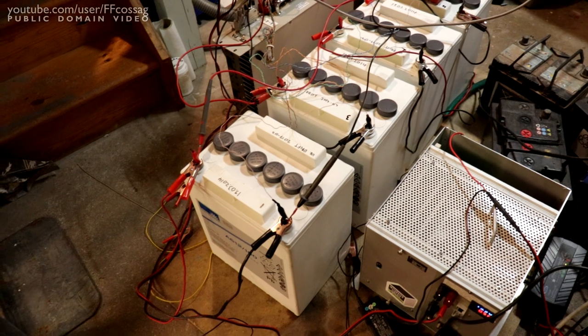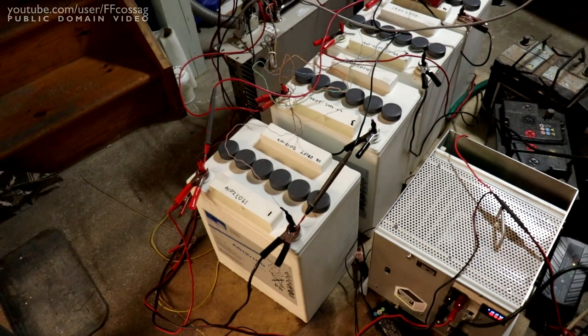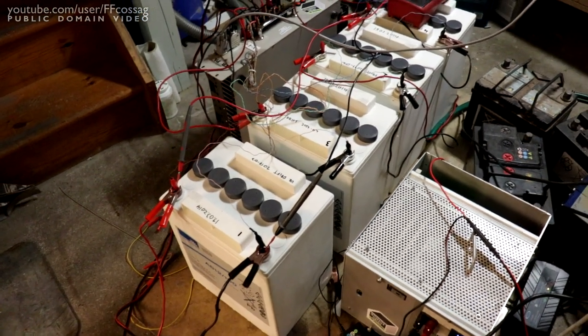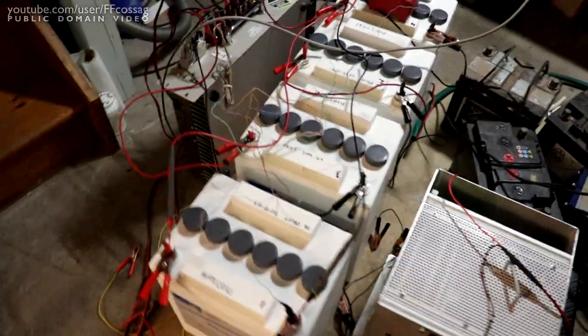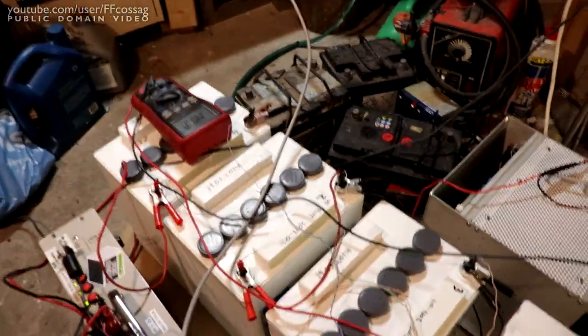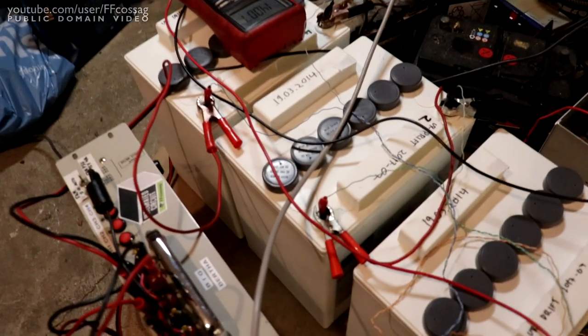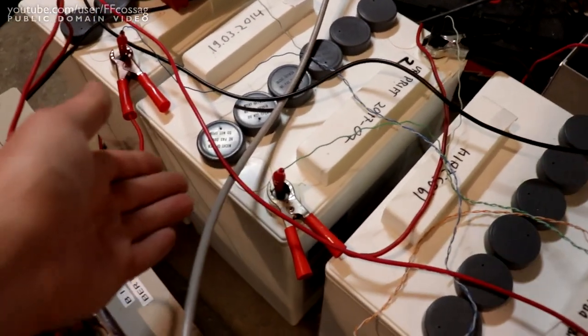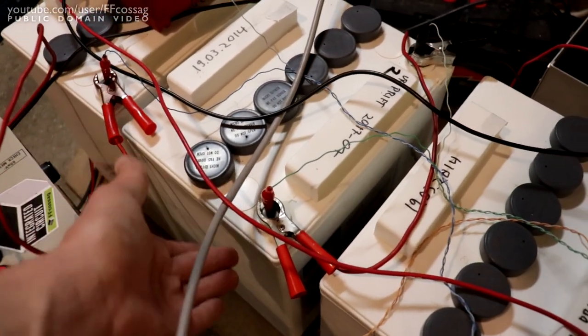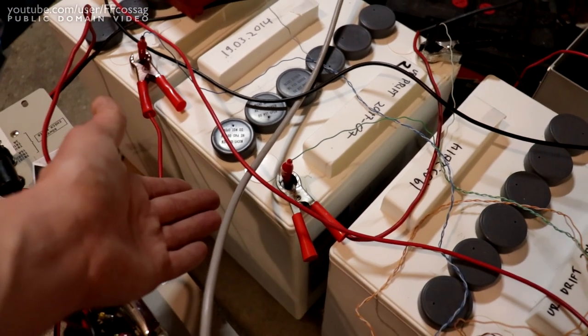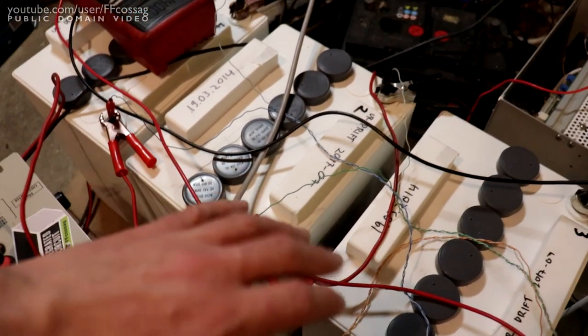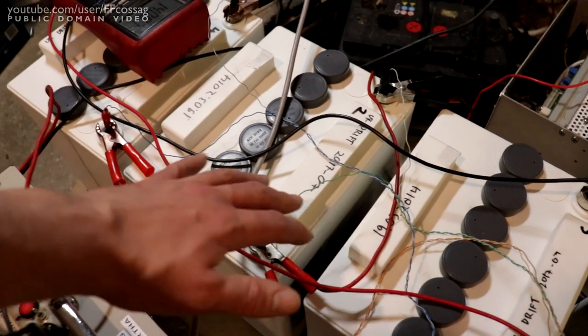Now, the 12-volt blocks in the A600 series are kind of notorious for leaking. I've seen it many times with these, and these are no exception. I have now cleaned these up, but in particular, number two here has a decent amount of leakage around the positive terminal. When I was lifting it up, it was just a big mess here.